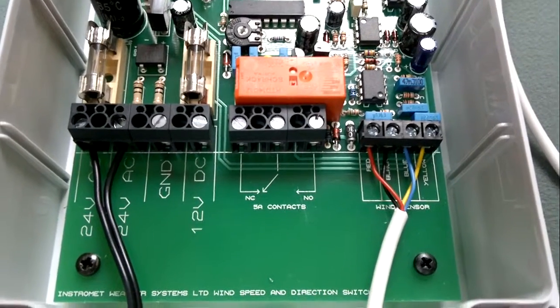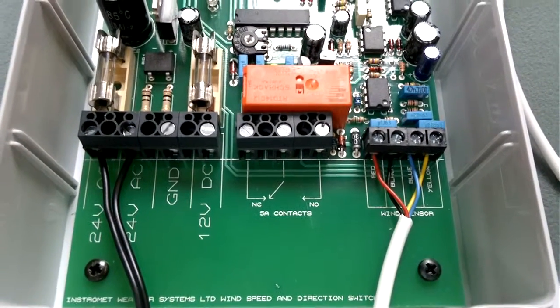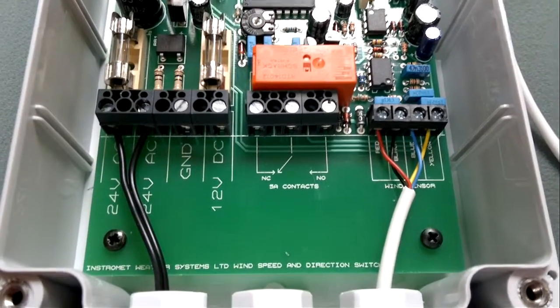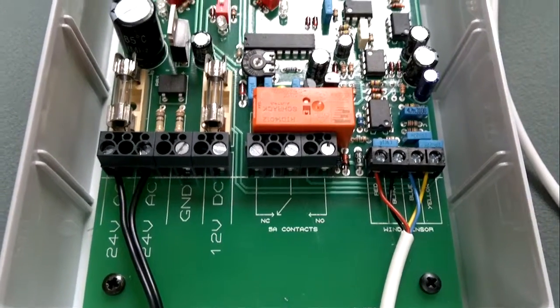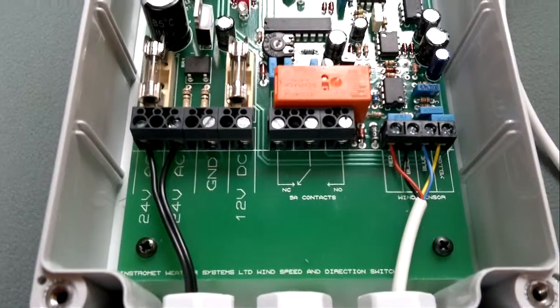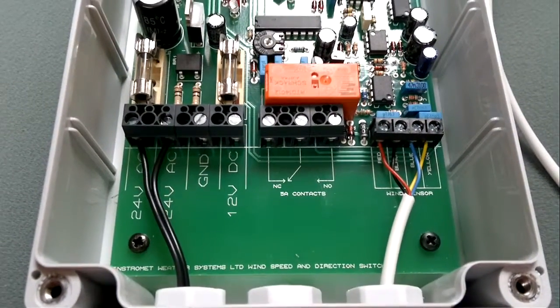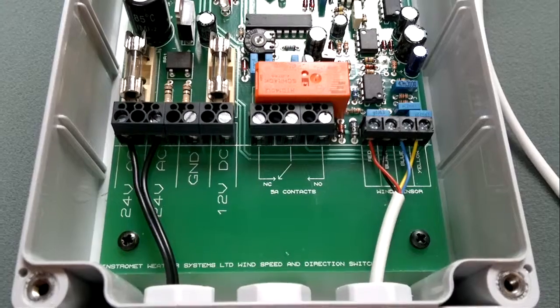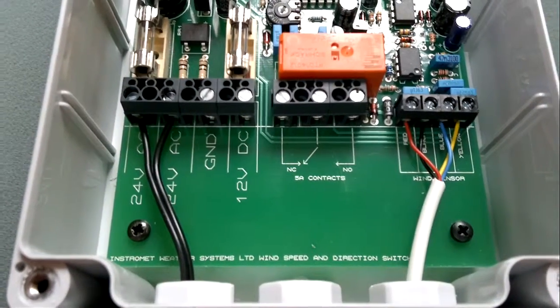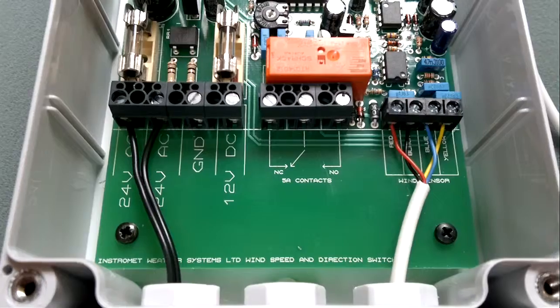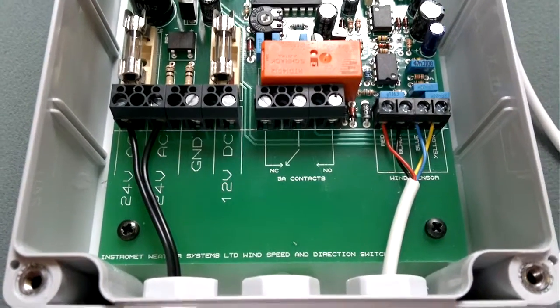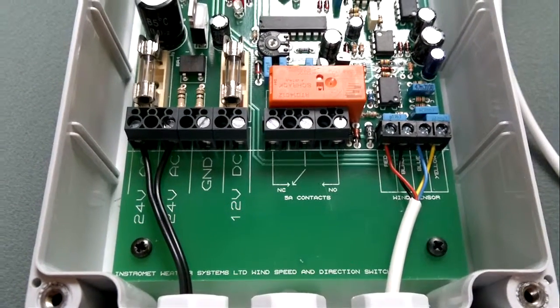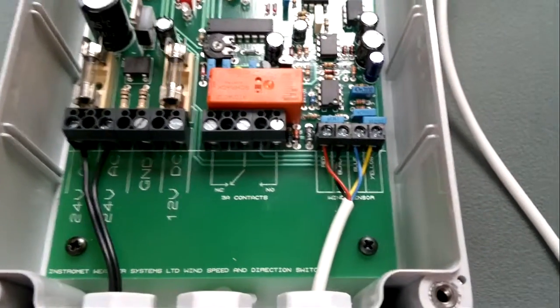You've then got next to that the switching terminals for the switch. It's rated at 5 amp contact but the terminals themselves are rated to 10 and the relay itself to 16. So although it says 5 it will go a little more if required. You've then got a terminal there for normally closed for the contact and normally open. So that being the case the unit can be used to either activate or deactivate a unit.